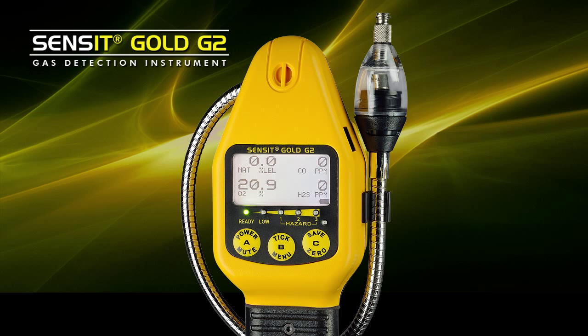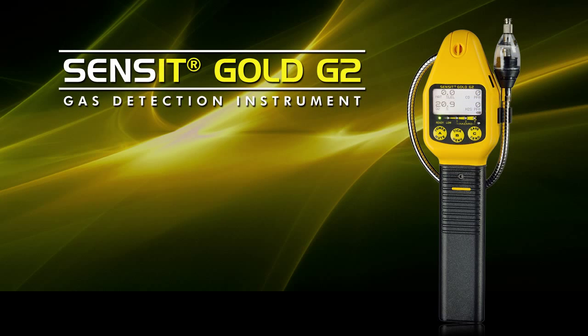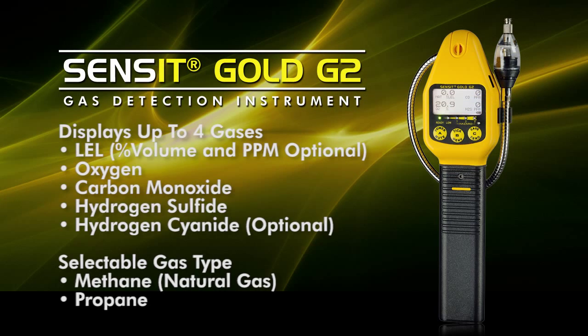Internally there is a pump that draws a sample through the instrument that comes across the LEL and parts per million sensor and then into the additional sensors located on the inside. The additional sensors include the toxics, the oxygen, and perhaps a percent by volume sensor depending upon your application.